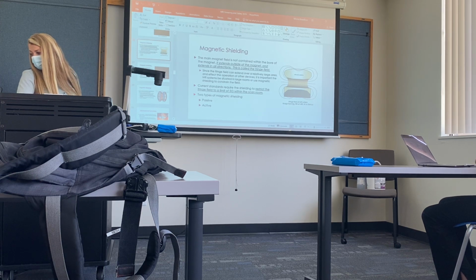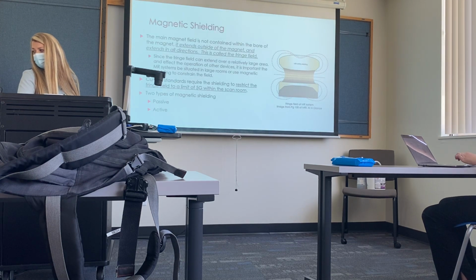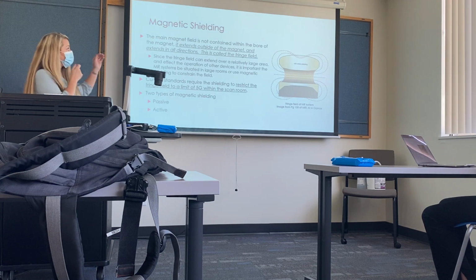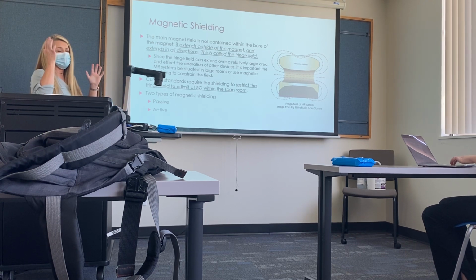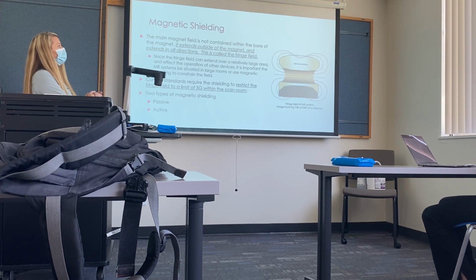All right, so we will pick up with where we left off, which is shielding. So, the main magnetic field is pretty powerful. We've talked about this. 1 Tesla, not very often will you see 1 Tesla anymore. 1.5 Tesla and 3 are the most common, but up to, in this country anyways, 7 Tesla.